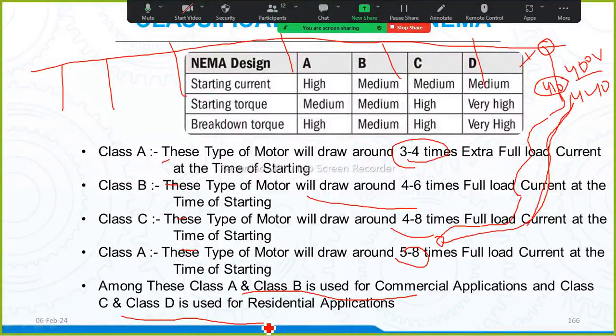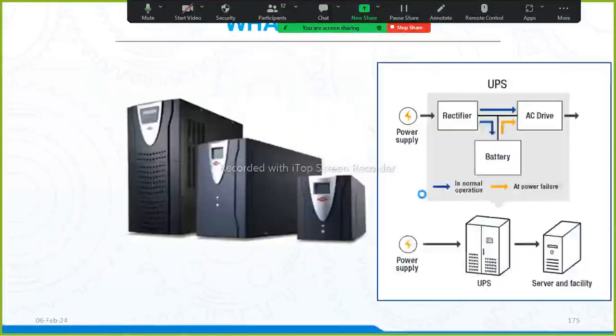But class A and class B are mostly preferred for commercial, because you'll get a higher rating, higher HP. Higher HP motors have lesser current taking capacity. So out of these I'm taking class A, which is 4 times extra. Now let us take this 4 times extra and check whether my transformer will be able to withstand that high power taken by the motor or not.